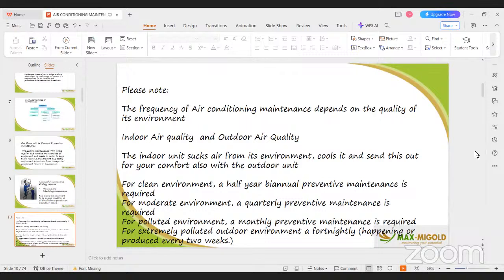For a clean environment, a biannual (half-yearly) preventive maintenance is required, depending on the cleanliness of your outdoor and indoor units. For a moderate environment, which is general practice everywhere in Nigeria, a quarterly preventive maintenance is needed, that is every three months. For a polluted environment, monthly preventive maintenance is required. For an extremely polluted environment, it should be done every fortnight, every one or two weeks.